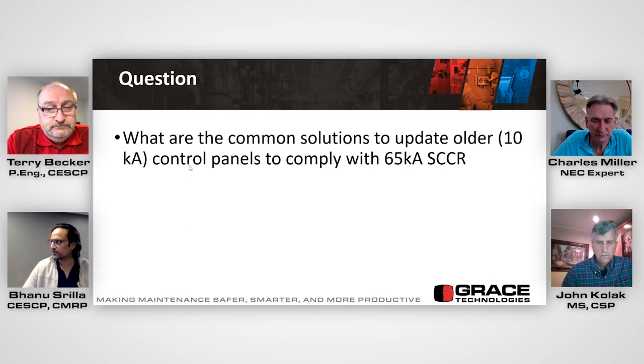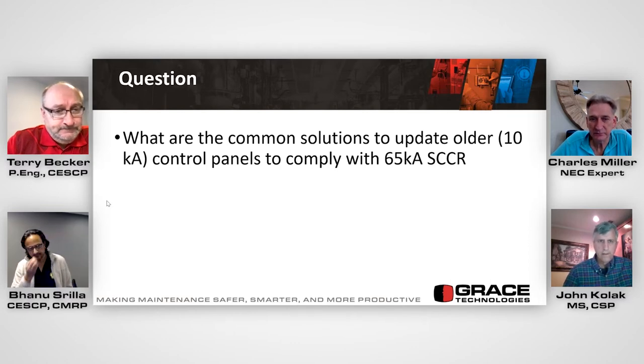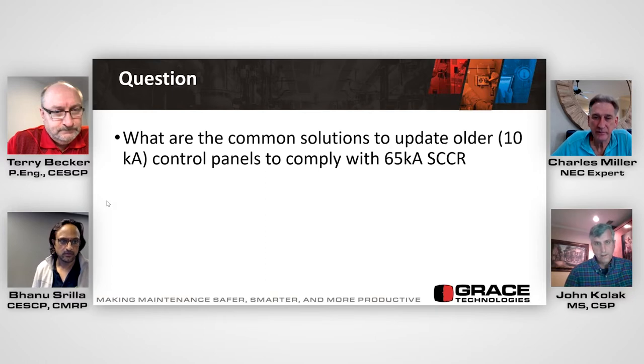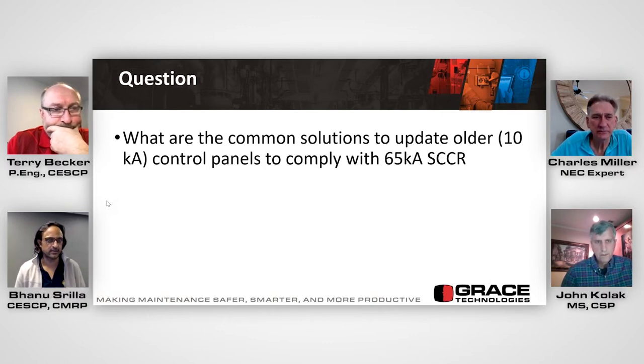What are the common solutions to update older, for example, 10 kiloamp rated control panels to comply with higher capacity requirements? Well, you don't need to update the panel if there's less than 10 kA there. The only requirement is that the overcurrent devices can interrupt the fault current and duration, so it's the interrupting rating. If there's only 5 kA, you don't have to do anything with the panel except make sure it all works at nameplate speeds. If it's higher than that, you'll have to upgrade the breakers and in some cases the conductors to handle the higher fault currents. But it's not really about the threshold of 10 kA necessarily, it's simply saying if you have a short circuit current, you have to be able to interrupt it at the nameplate speed.